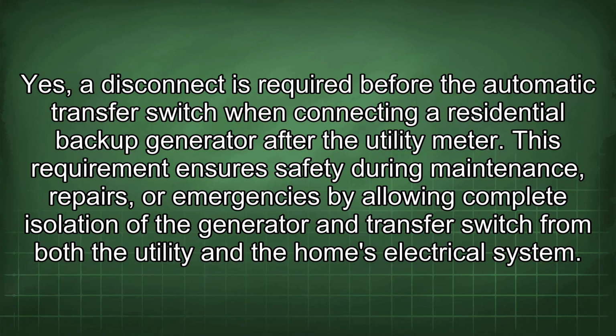Yes, a disconnect is required before the automatic transfer switch when connecting a residential backup generator after the utility meter. This requirement ensures safety during maintenance, repairs, or emergencies by allowing complete isolation of the generator and transfer switch from both the utility and the home's electrical system.